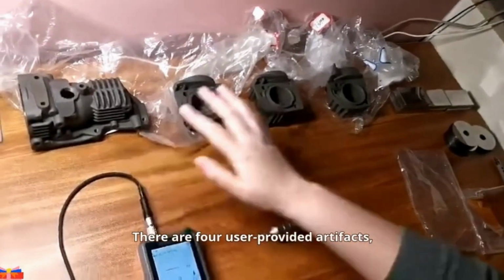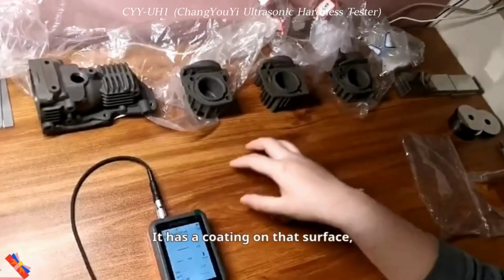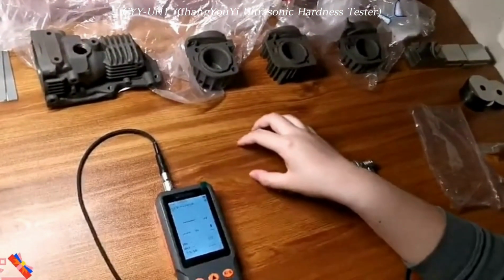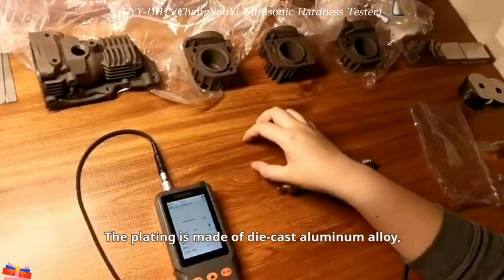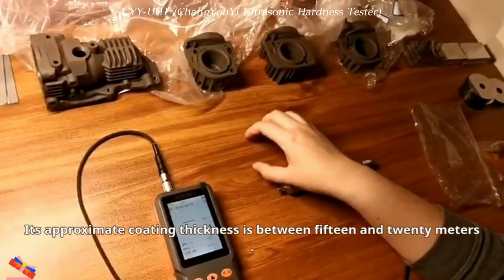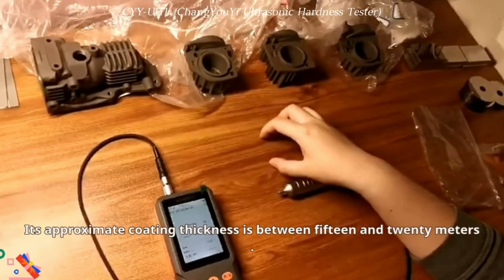Okay, today I'd like to bring you a case of an ultrasonic hardness tester on a user's workpiece. There are 4 user-provided artifacts. It has a coating on the surface. The plating is made of die-cast aluminum alloy. Its approximate coating thickness is between 15 and 20 micrometers.